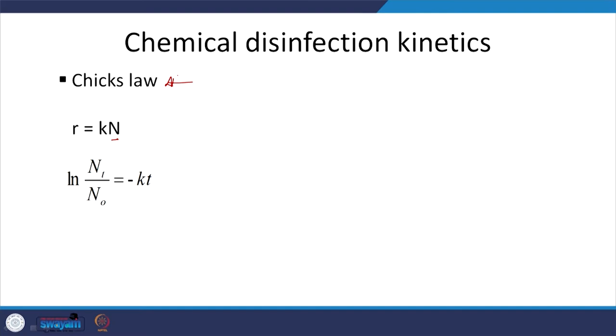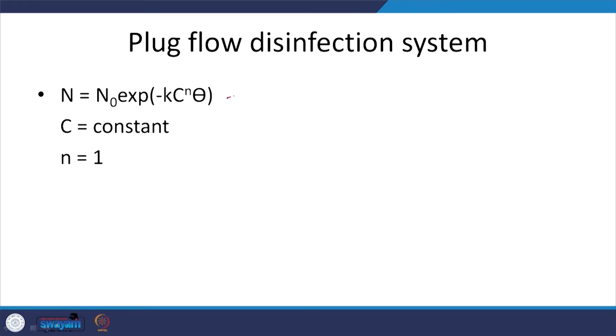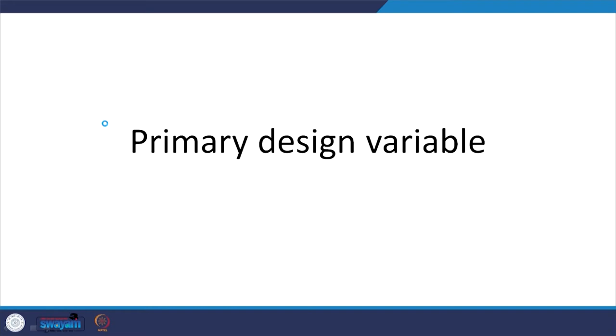The first law we looked at was Chick's law, which only considers the concentration of microbes as determining the rate. But the concentration of the disinfecting agent is also important, so Chick-Watson's law takes both the microorganism concentration and the disinfectant concentration into account. We also looked at plug flow — why it is better — and how to derive the relevant equation, including actual pictures of disinfecting systems.